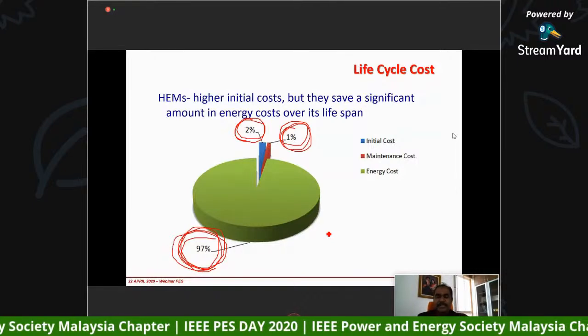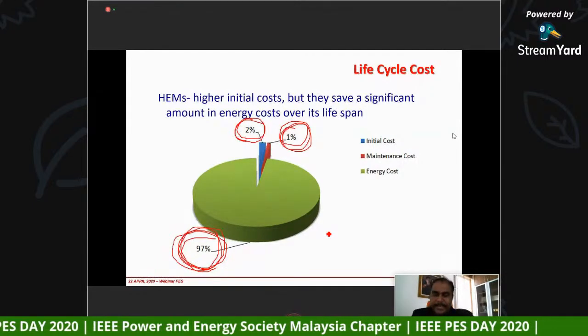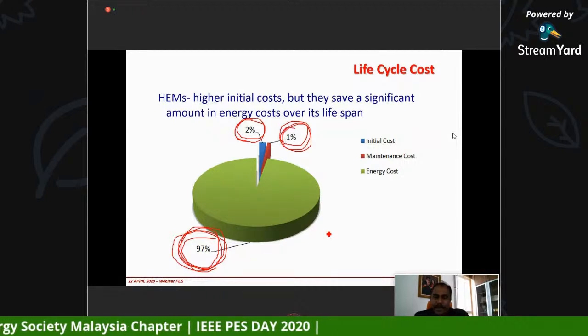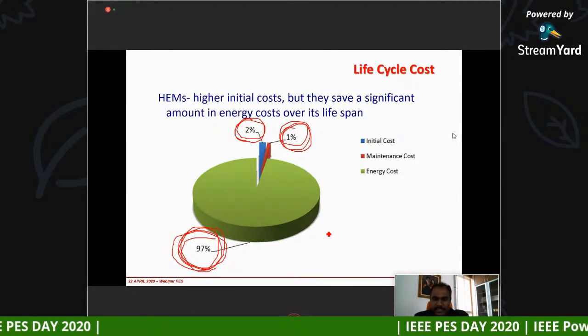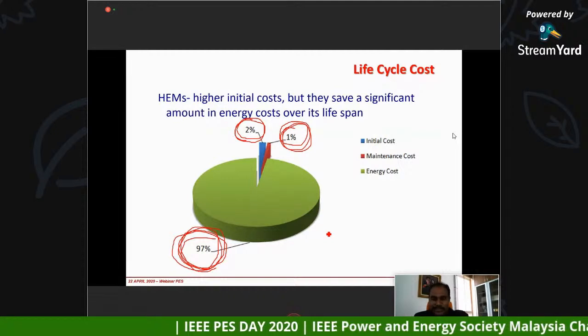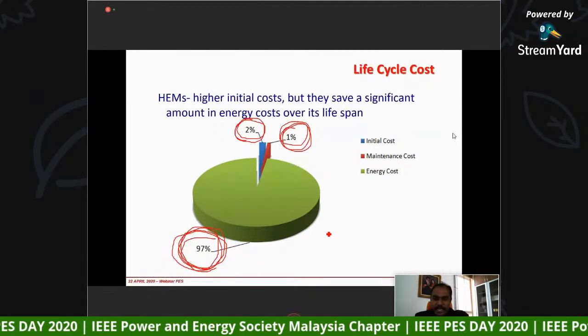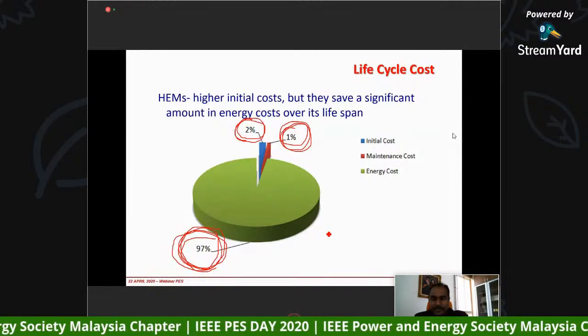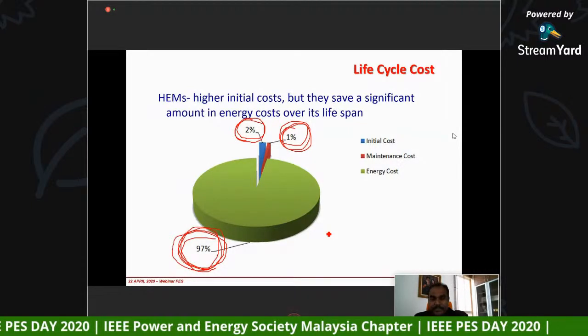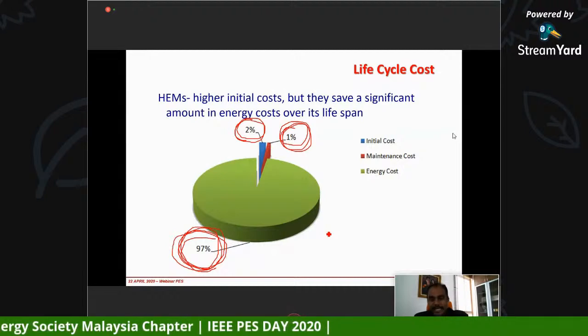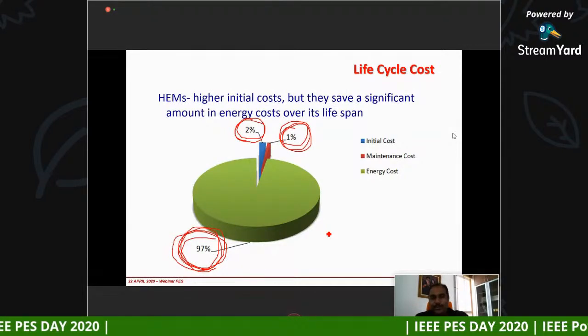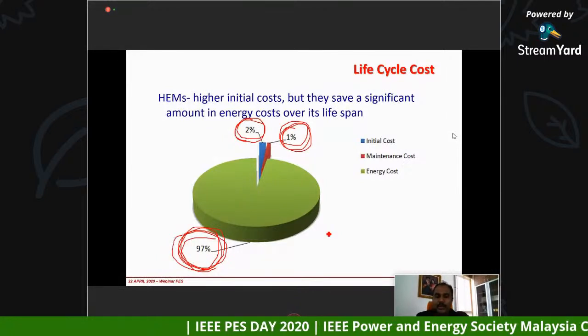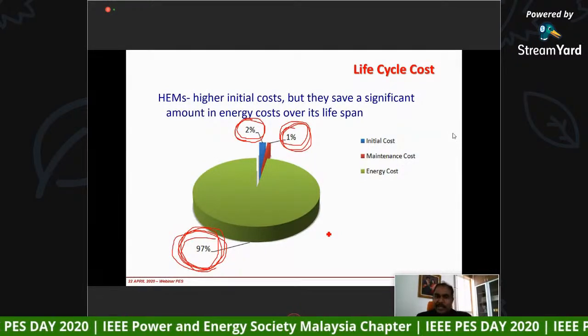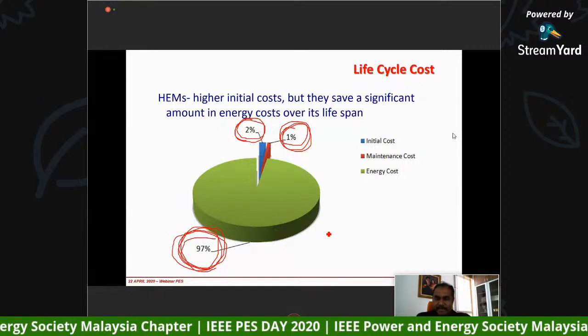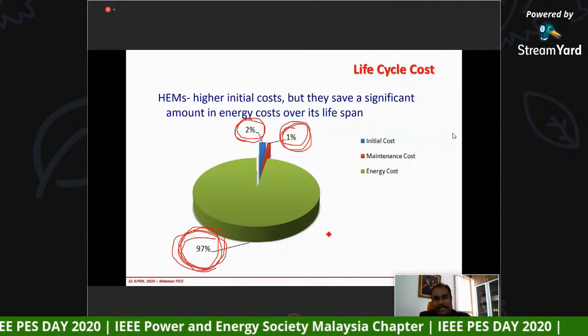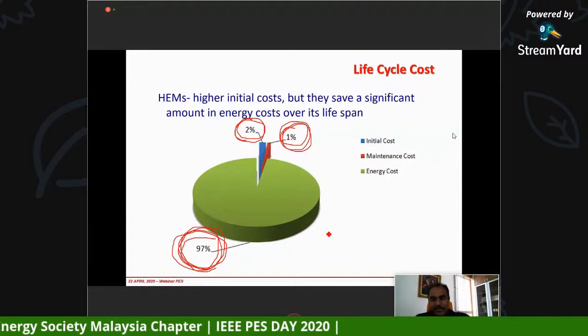But then if you put it in the life cycle cost, that means if you actually confirm that by going for IE3 motors, which in the next slides I will tell you what are the do's and don'ts when you are selecting the high efficient motors. Let's say you confirm going for IE3 motors and you know that saving is going to be there in terms of energy savings, then you actually can calculate what is the energy cost per month for that particular motor that you will save. And then every time you buy a motor, you will be able to use the motor for an average of at least 15 to 20 years.